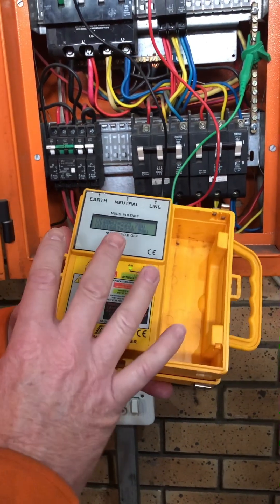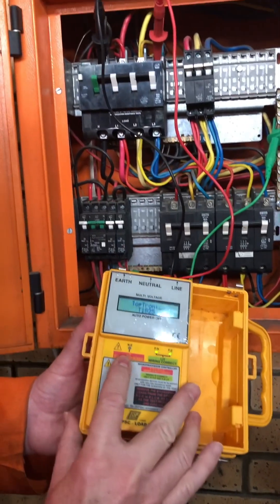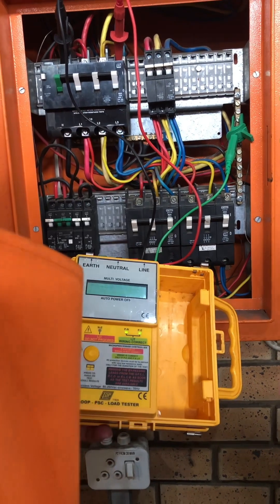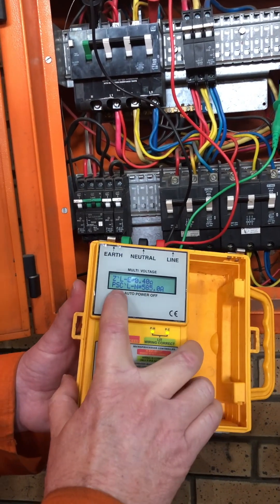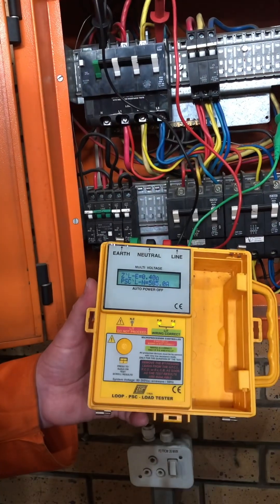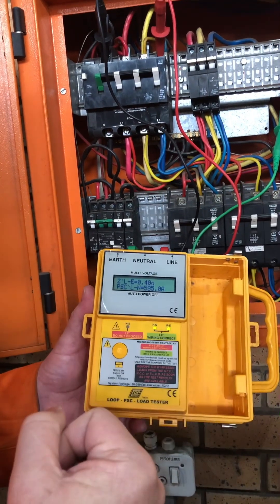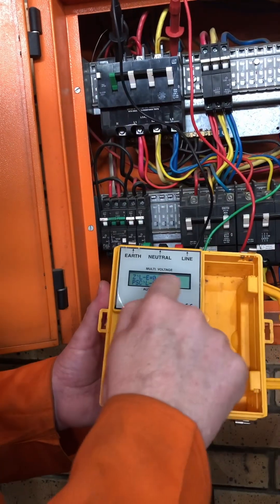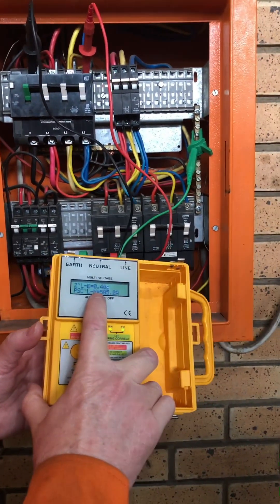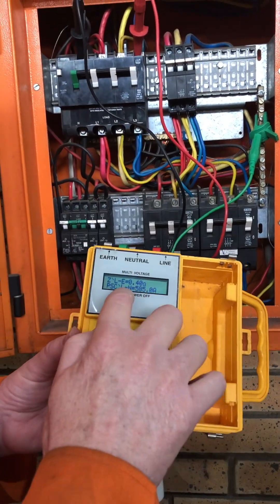It can hold the memory, but not for long. So it gives you those voltages. I'm just gonna do it again — you will see it will be different. The PSC now is 500 amps. Because Eskom is pushing up power, lowering power — supply and demand. When demand goes up it will be more, when demand goes down it will be less. So that 585 amps is what it's measuring now.